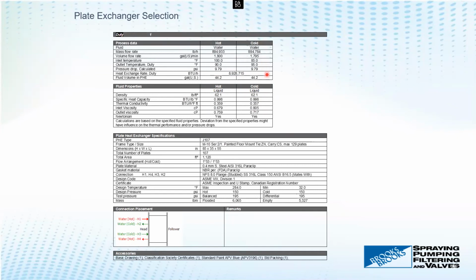The rest of this is essentially what we'll be able to tell you. So if you can handle 10 PSI pressure drop, which just under 10 is what this calculation gave us, that's 9 million BTUs per hour, which is a tremendous amount. This is all sort of from the process data here.